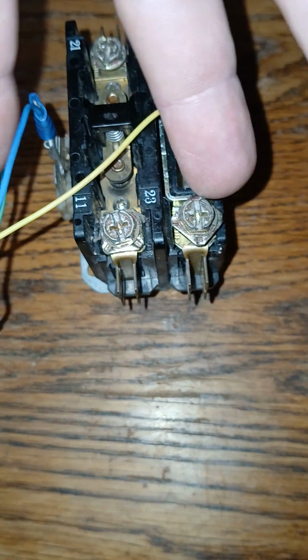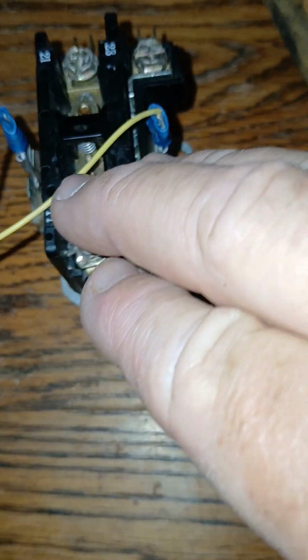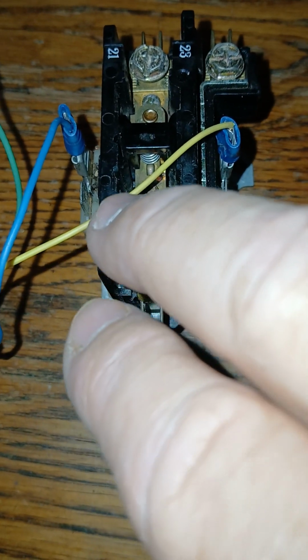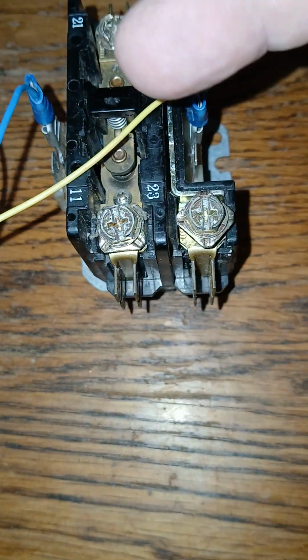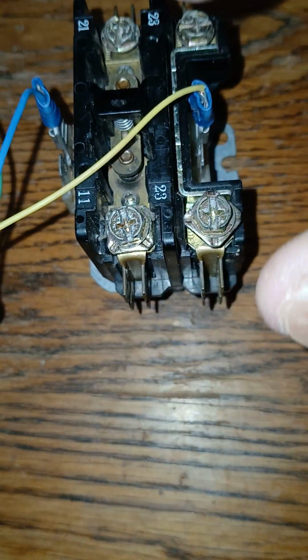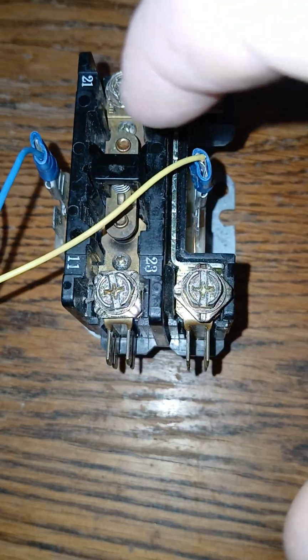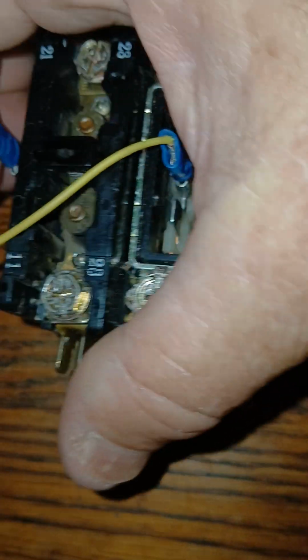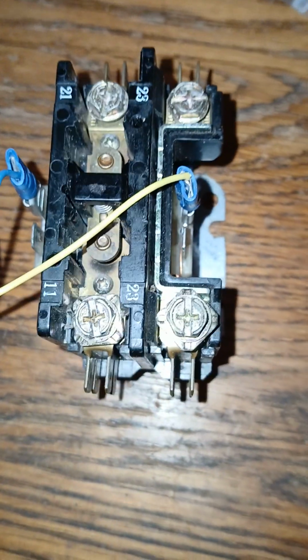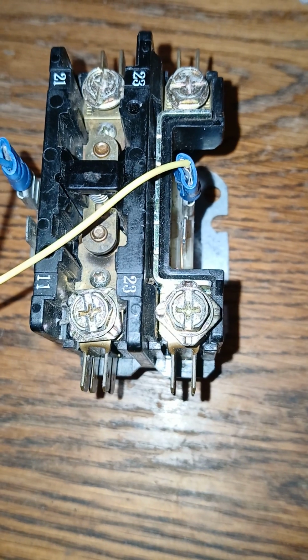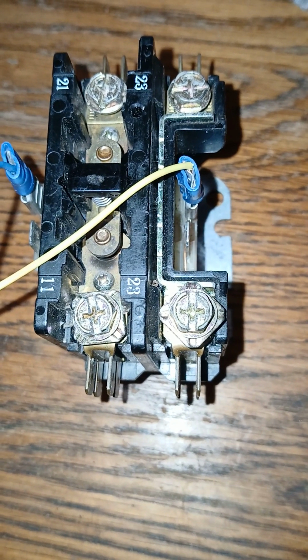But basically, we're putting 24 volts here. We've got a hot and a common. Do keep in mind now, some people will wire from the terminal strip in the air handler, a red wire in this. So if you see a red wire on here, don't be alarmed. Basically, they may tie this in on the terminal strip at the heating and air. So basically, this would be your hot wire, this would be your common, this would be your incoming voltage, this would be your return voltage. And what this would do when the thermostat calls for cooling, it would simply energize this. When it energizes this, the coil on the bottom, as one can see here, that coil there will be energized, and the voltage will jump over there. So this is one way you could wire the low voltage up to a contactor to engage low voltage to high voltage.